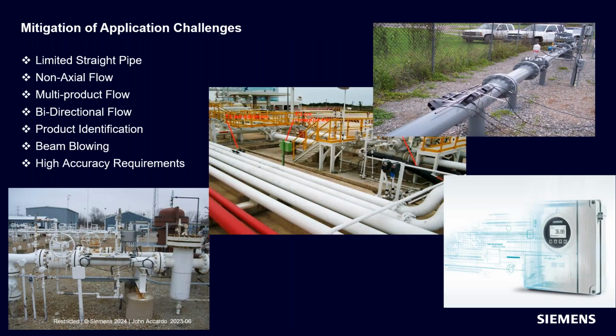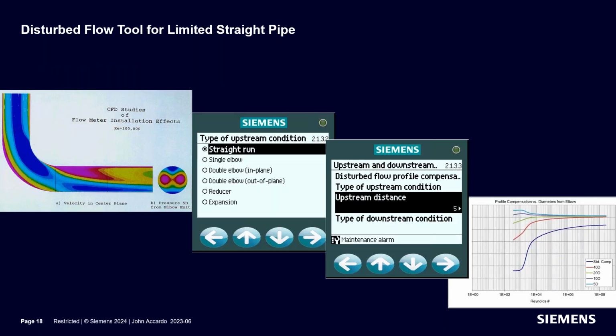So all of these things I've been covering up till now are some of the problems that we face in the field as a clamp-on flow meter. And we have ways to mitigate these things. So looking at some of the things that we're up against, we have limited straight run of pipe, which I just talked about, non-axial flow conditions, multi-product flows, bidirectional flow, product identification, beam blowing with gas applications, and high accuracy requirements. And maybe all of these things in one application. Being able to handle that is a key part of how good your flow meter really is.